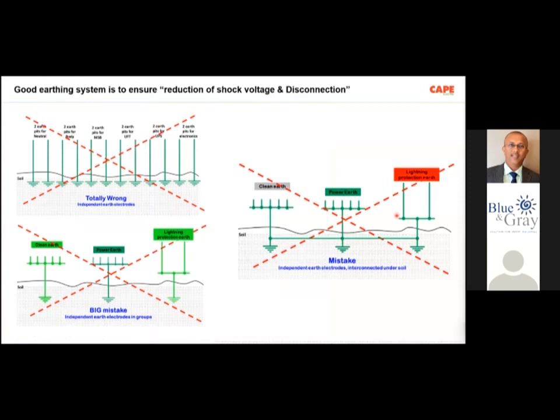Now, but whenever it comes to good practices in earthing, what do we do? We have a lot of earth electrodes in soil, which I always say is a mistake. You are not supposed to have so many earth pits in your building. One building sometimes requires only one earth electrode. You don't need to have so many earth electrodes.